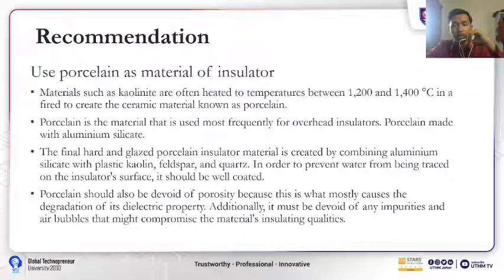In order to prevent water from being traced on the insulator surface, it should be well glazed. Porcelain should also be devoid of porosity because this is what mostly causes the degradation of its dielectric property. Additionally, it should be devoid of any impurities and bubbles that might compromise the material's insulating qualities.